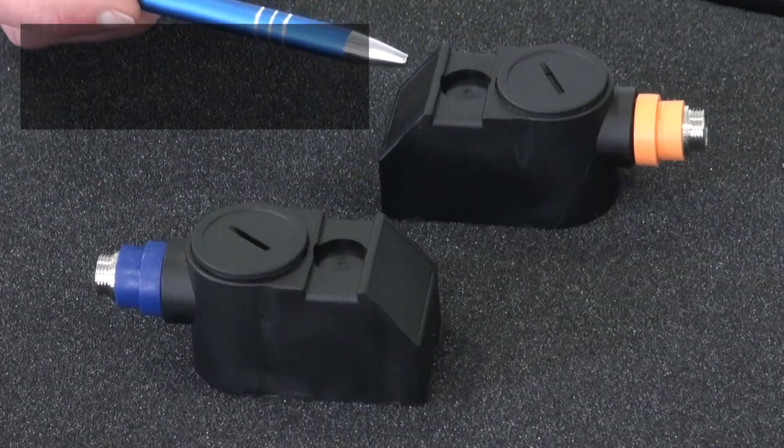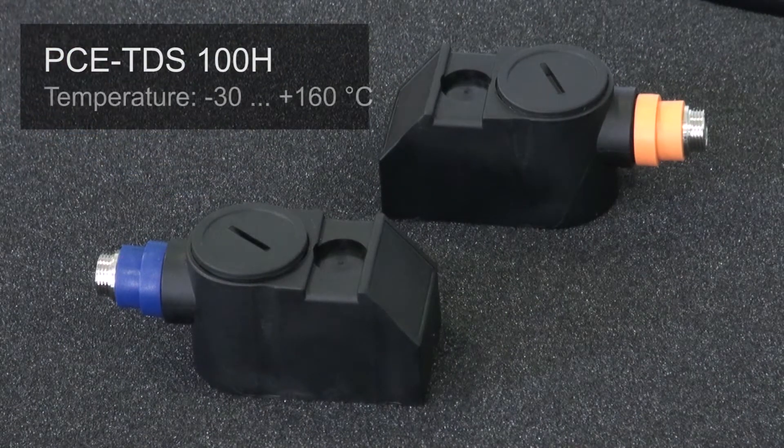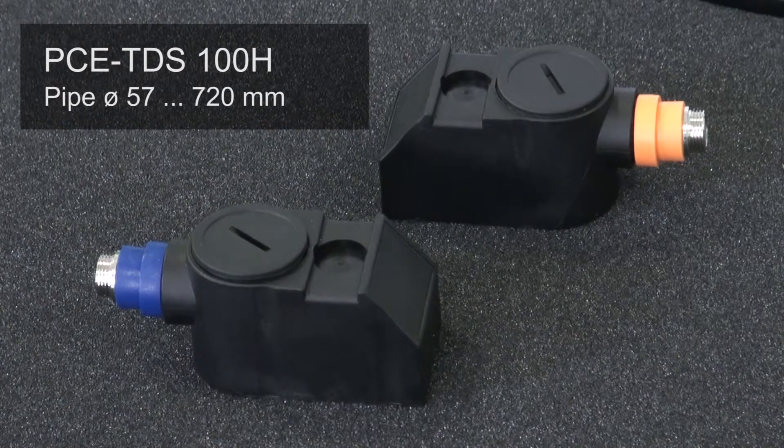The sensors of the PCE-TDS 100H work in the same temperature range and are designed for nominal diameters from DN 50 to DN 700, corresponding to inside diameters from 57 to 720 millimeters.